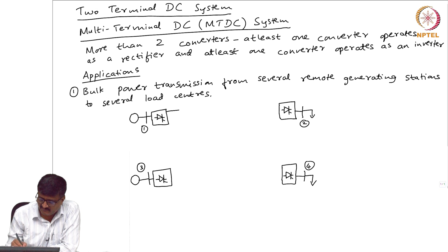Now, let us see how to do an interconnection such that the number of converters required is shown to be just 4, and this is less than 8, which was required for making the same amount of connections using two terminal DC systems. So, the DC side will have 2 wires. I show the 2 wires, positive and negative.